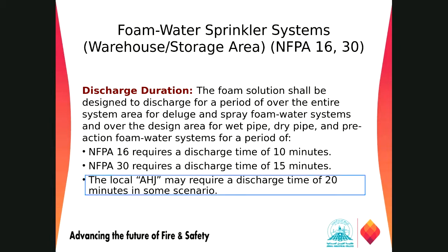As for NFPA 16, we have to follow 10 minutes. If you have to follow NFPA 30, which is the flammable and combustible liquids code, we have to go for 15 minutes. And sometimes we have to coordinate with the local department teams to get the exact scenario.